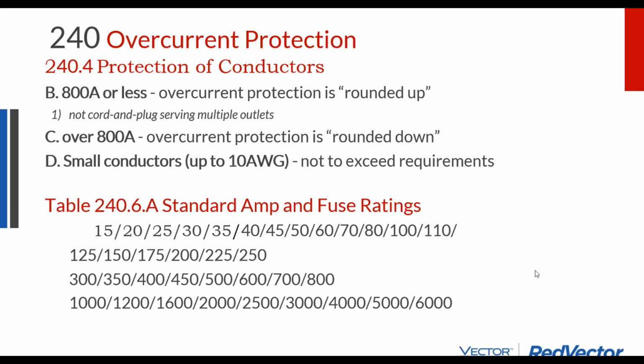And so it's like, well, what does that mean? If I get 19 amp cable and I put it on a 20 amp breaker, couldn't I have one extra amp and burn up my cable, but the breaker doesn't trip? Well, in reality, we don't get that granular. So you're probably going to be looking for 19 amp cable, but only be able to find 20 amp cable. What happens is when you get over 800 amps, your fuse and breaker sizing stops being so granular. You don't get such resolution. And so that problem only becomes an issue when you get over 800 amps.